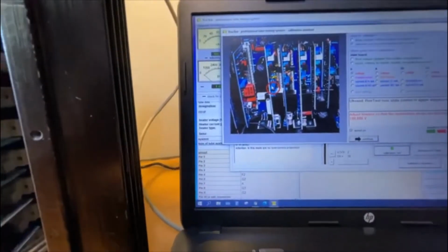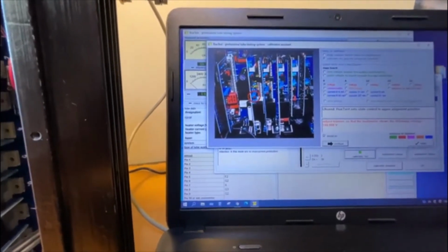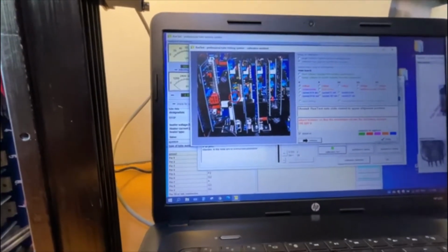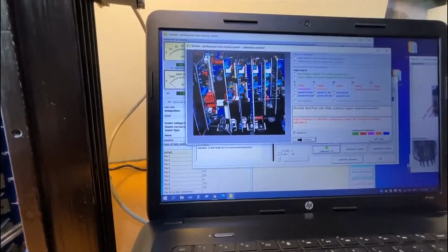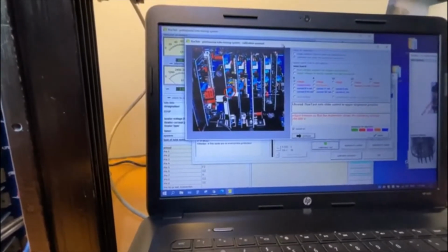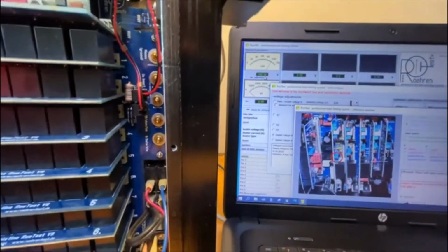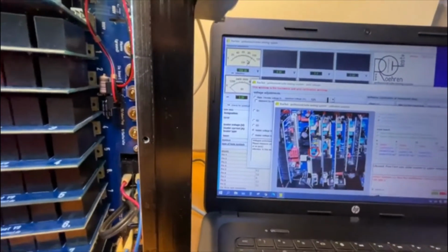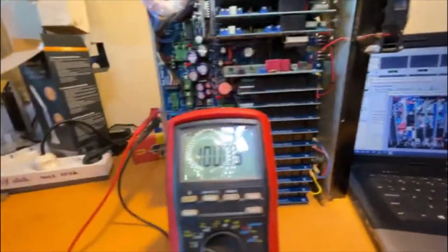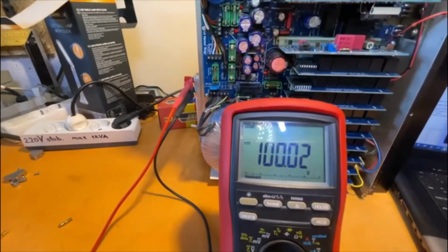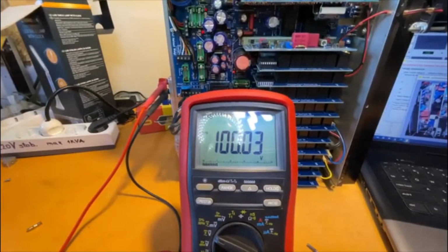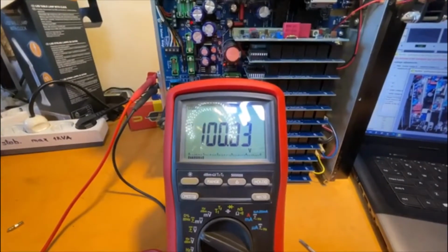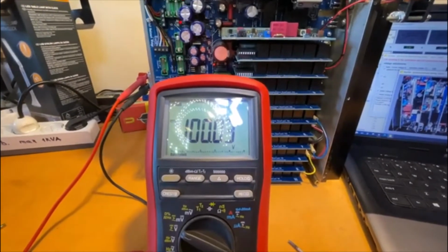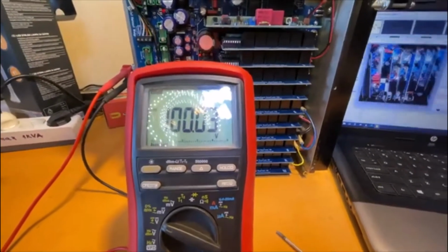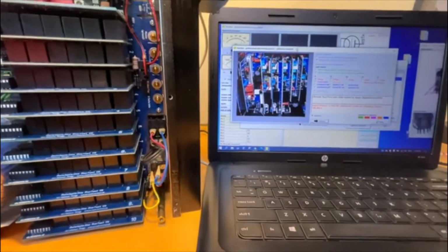It shows us to adjust this trimmer. How nice. It showed us in the picture where we need to make the adjustment. So you must adjust the trimmer so that the multimeter shows the following voltage: 100 volts. As you see here on this voltmeter, we have 100 volts. It's okay. And on the multimeter, it's 100.02. Wonderful. The last calibration was made 4 or 5 months ago, but I checked it from time to time, 1 or 2 times per month. This is okay.